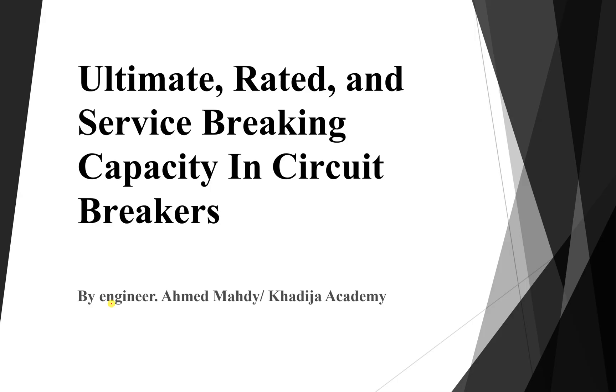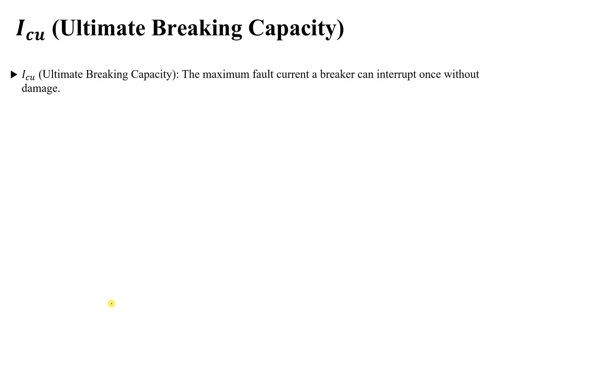In circuit breakers there are three definitions which are very important to understand. The first one is called the Ultimate Breaking Capacity. According to the IEC standard, ICU, or the Ultimate Breaking Capacity, represents the maximum fault current a breaker can interrupt once without damage. This means our breaker is designed to interrupt this fault only once.